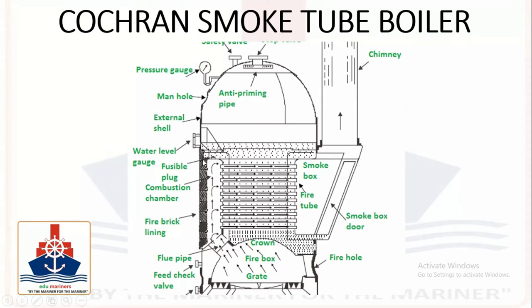The combustion chamber top requires support, so gusset stays are provided which transfer the stress from the flat top of the combustion chamber onto the boiler shell. The flat tube plates are tied together by means of stay tubes which are screwed into the smoke tube section.